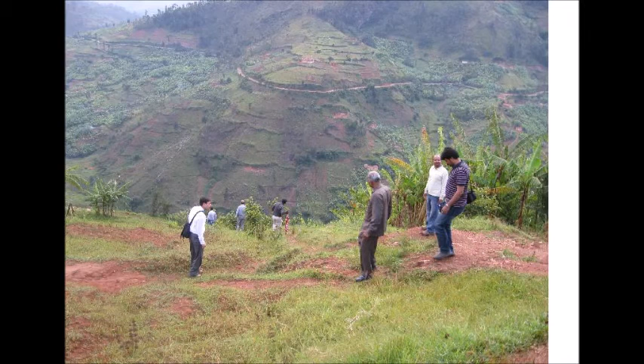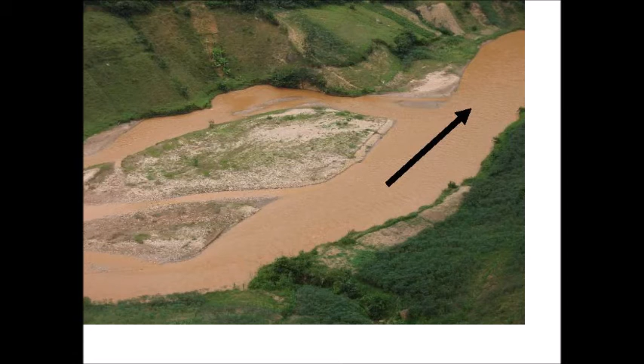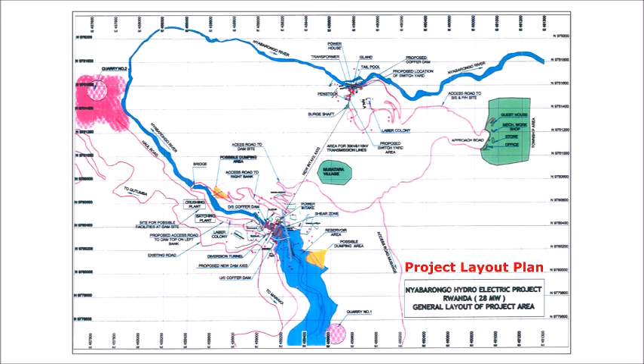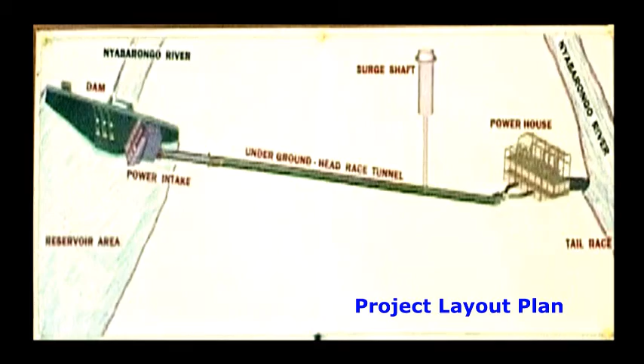The Nyabarongo hydroelectric project involves construction of about 44.5-meter high concrete gravity dam located at the starting of the river loop of Nyabarongo with intake structure located at the right bank of the river. A 1.2-kilometer long HRT, surge tank and a surface powerhouse on a terrace on the right bank of the river utilize the gross head of 63 meters for generation of 28 megawatt power.